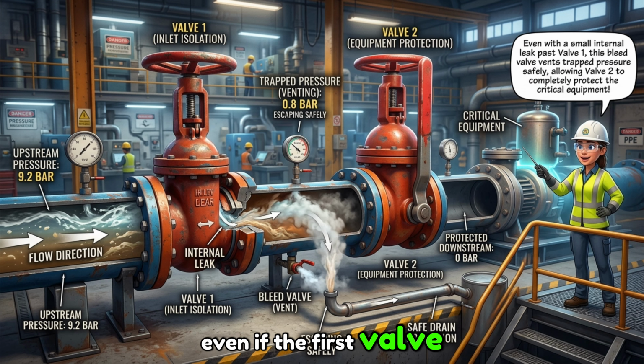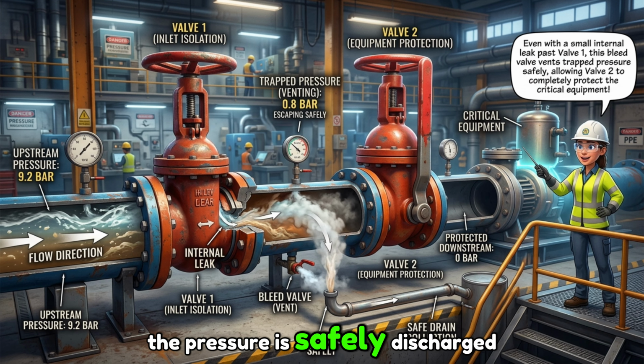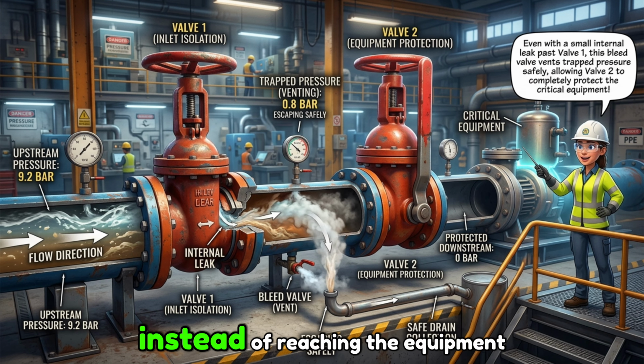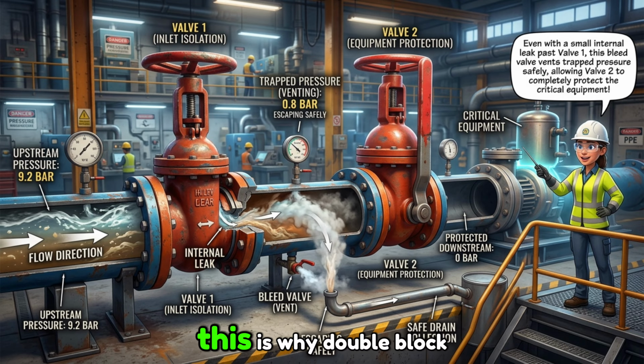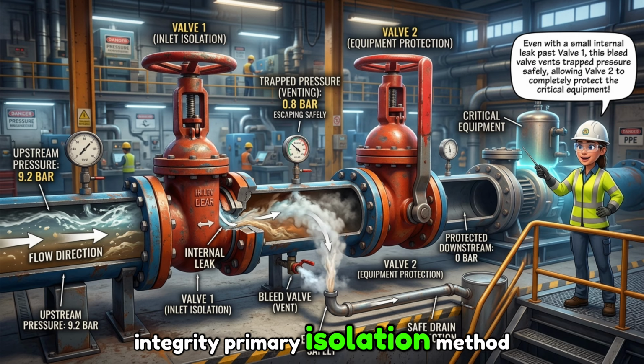Even if the first valve leaks slightly, the pressure is safely discharged through the bleed valve instead of reaching the equipment. This is why double block and bleed is considered a high-integrity primary isolation method.